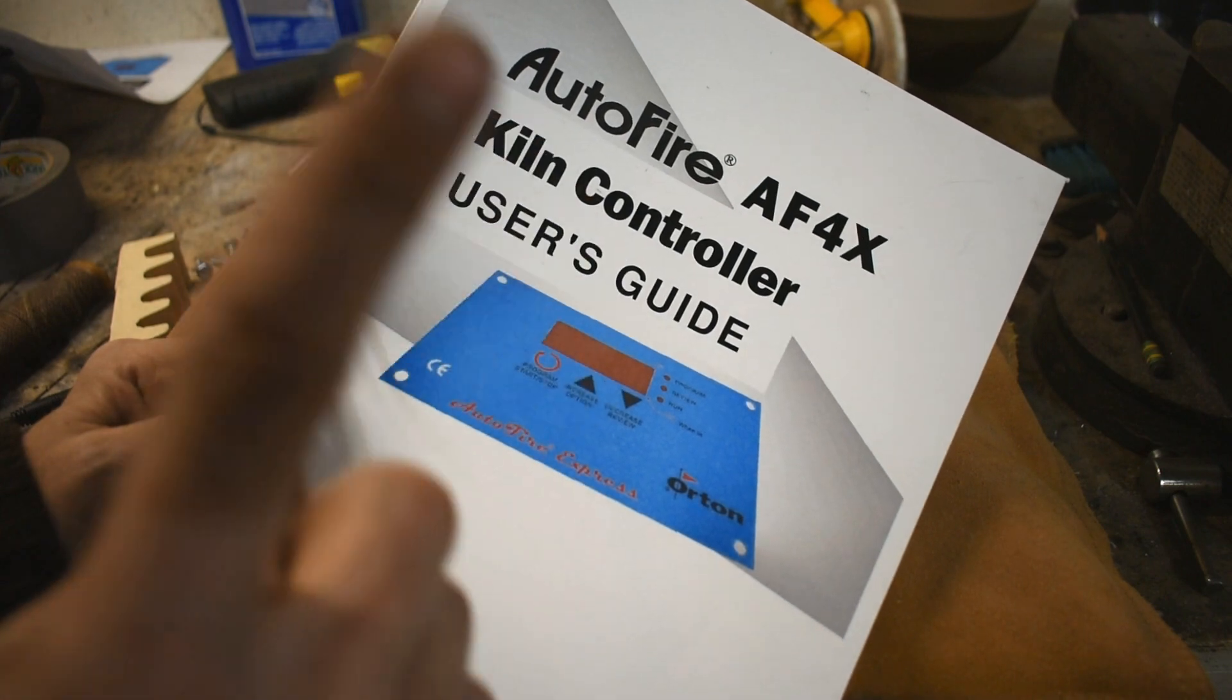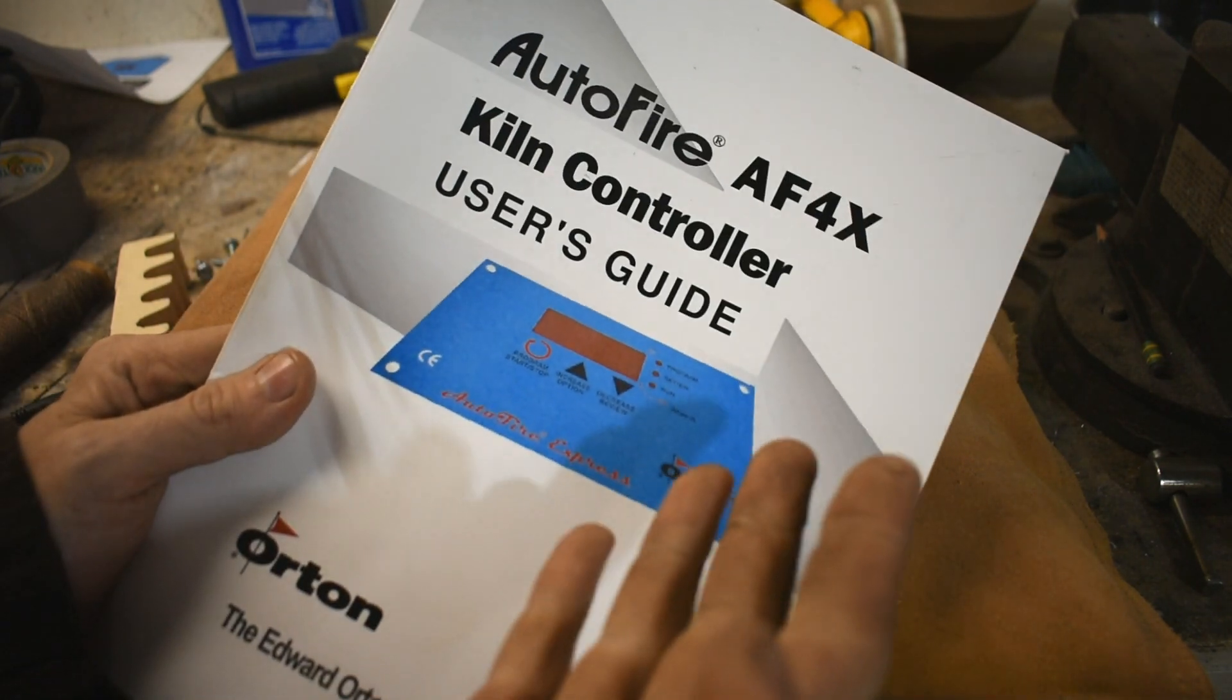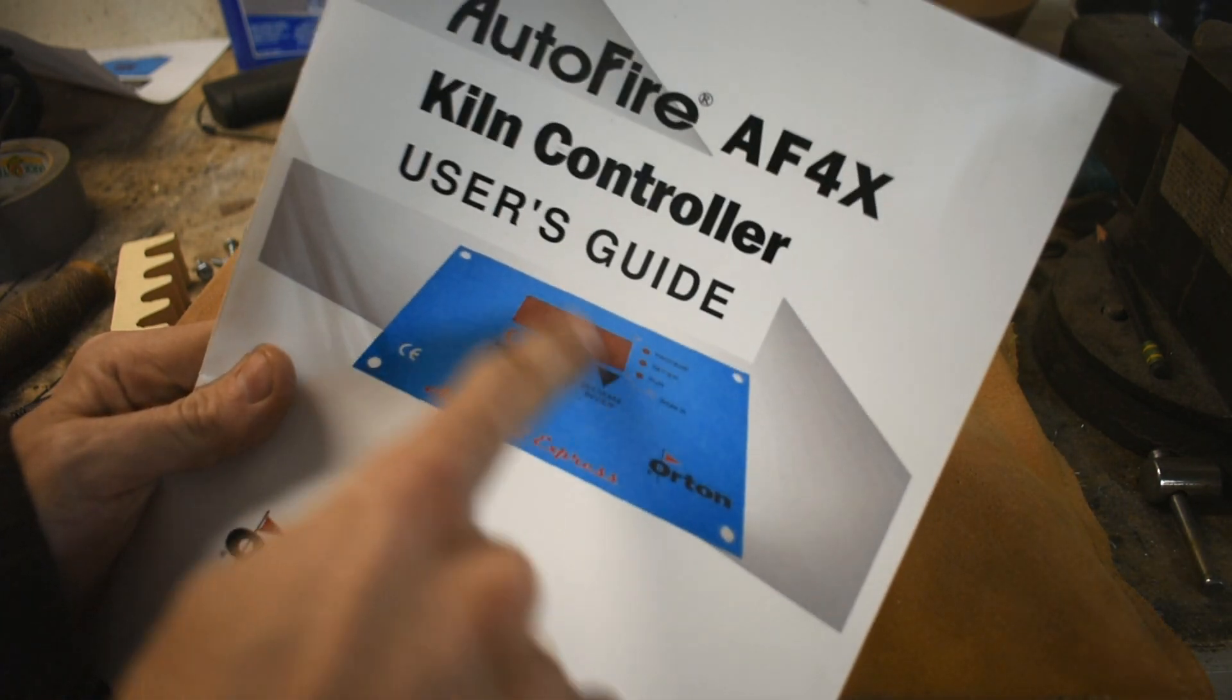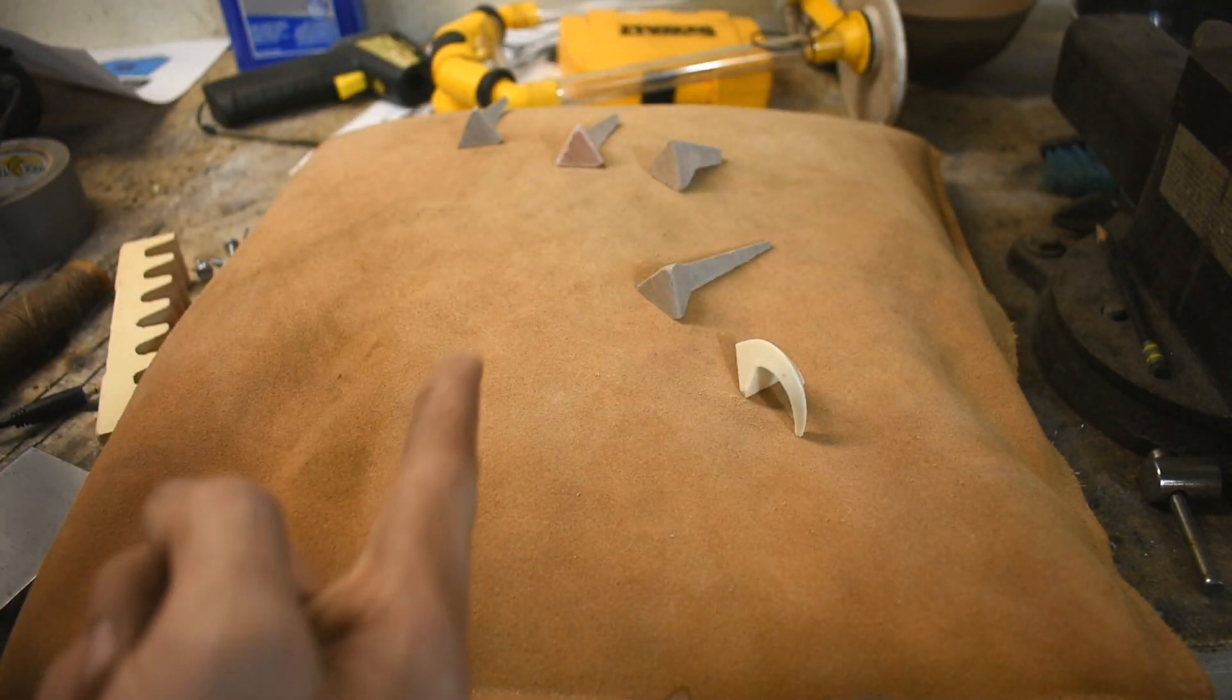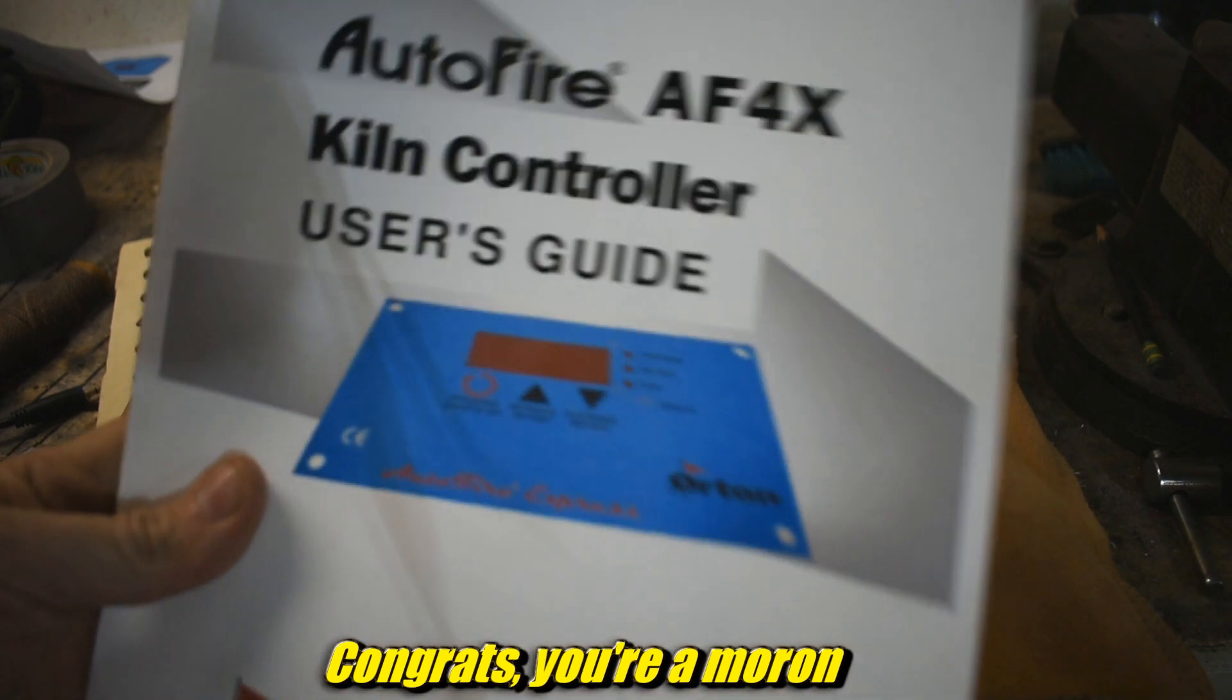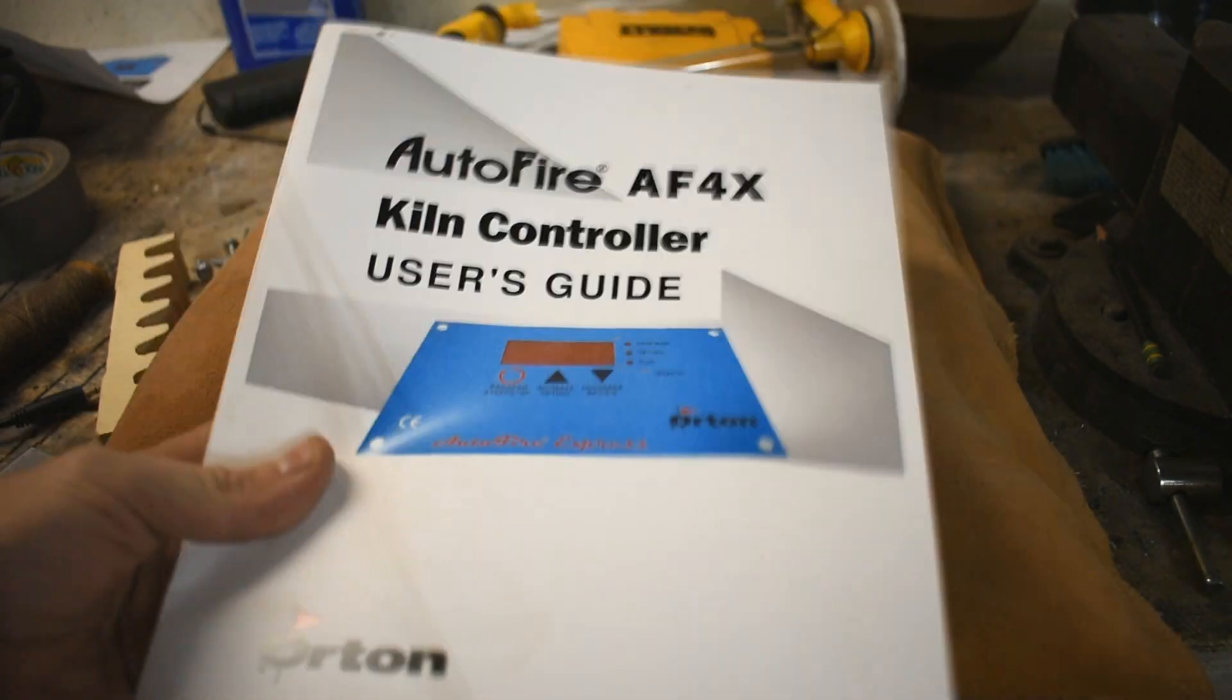I saw that it was set for type K and I didn't want to mess with it because type K is what I had. When I checked it, it wasn't set for type K, it was set for some other one. So I had inadvertently, in my fumbling around with these buttons, set it for some other kind of thermocouple and basically screwed myself over for all of this time. Read the manual is important, sure, but double-check all the settings, even the ones that are obviously not going to be wrong, because it might be wrong.